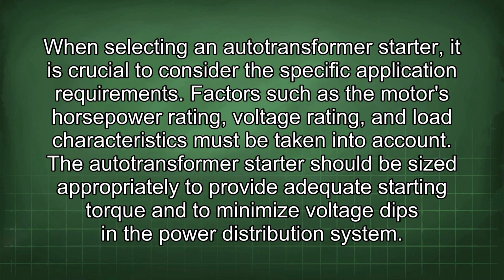When selecting an autotransformer starter, it is crucial to consider the specific application requirements. Factors such as the motor's horsepower rating, voltage rating, and load characteristics must be taken into account. The autotransformer starter should be sized appropriately to provide adequate starting torque and to minimize voltage dips in the power distribution system.